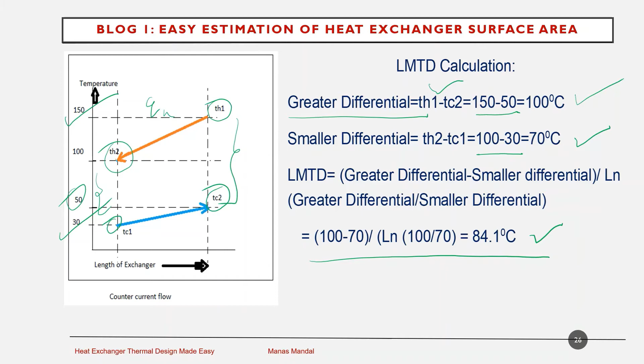In co-current flow, the same calculation can be done. Here, the greater differential is TH1 and TC1. TH1 minus TC1, 150 minus 30 gives us 120 degrees C. Smaller differential is TH2 minus TC2, 100 minus 50, 50 degrees C. So finally it is giving us 120 minus 50 divided by ln 120 by 50 is giving us 79.95 degrees C, which is lower than counter current flow exchangers.